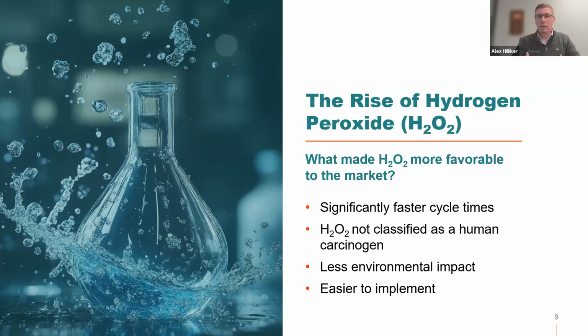Of course, hydrogen peroxide is marketed as a much safer alternative to ethylene oxide. Hydrogen peroxide does not have the same monitoring and ventilation requirements that ethylene oxide does. Generally speaking, the health impacts, the chronic exposure impacts, are less severe with hydrogen peroxide than ethylene oxide. And it's very easy to implement. Really, the hydrogen peroxide sterilizers that we're using today are generally plug and play. You need space and power. So you can easily see why hydrogen peroxide now dominates the market.